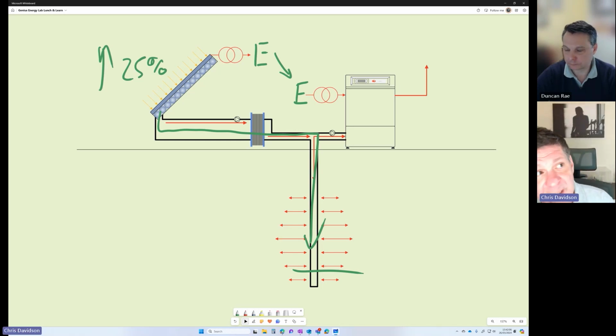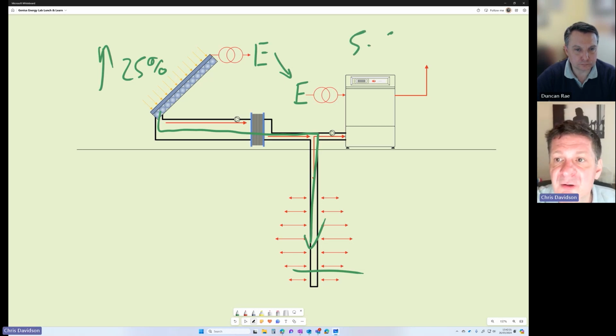Our test system, running for about 4 years now, is improving the seasonal COP - I'll come back to that in a minute - from a typical heating-only ground source system of 3.5 to 4, up to 5.5 seasonal on that system. I'll come back to COPs in a second.